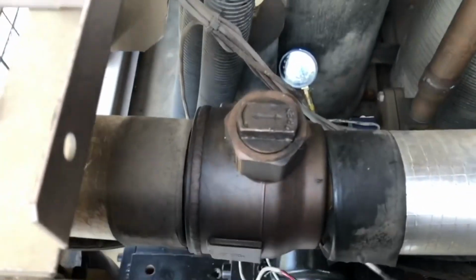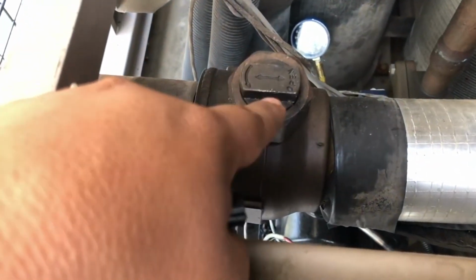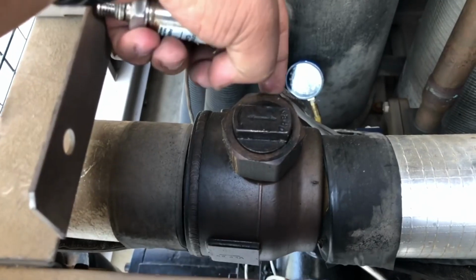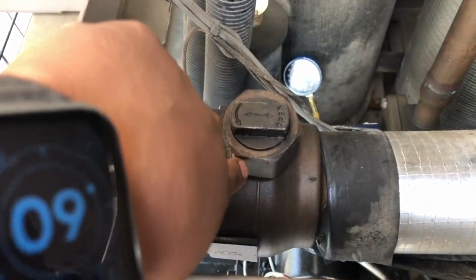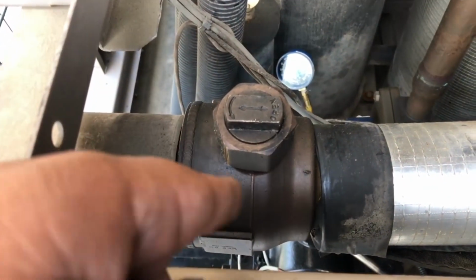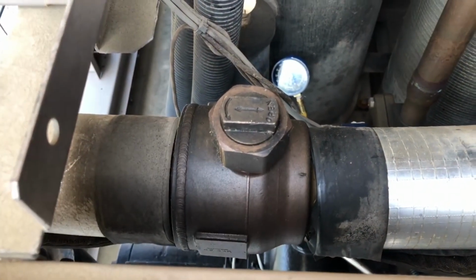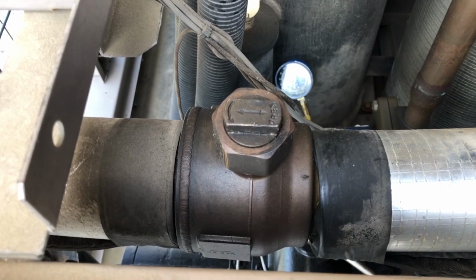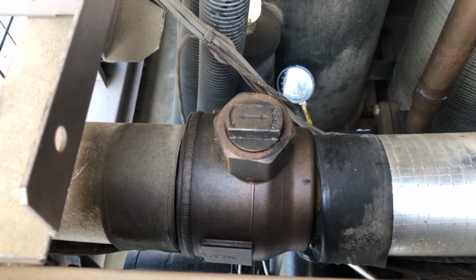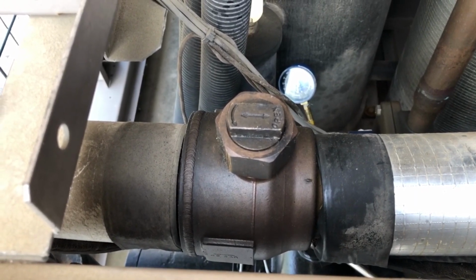Let me show you something, let me get up here. So whenever you mess with this valve, you open it and close it, make sure this cap doesn't get loose. Make sure it doesn't get loose. It happened to me once - I was working with that valve, and it got loose, and I got refrigerant oil spilling out when the pressure's still up.